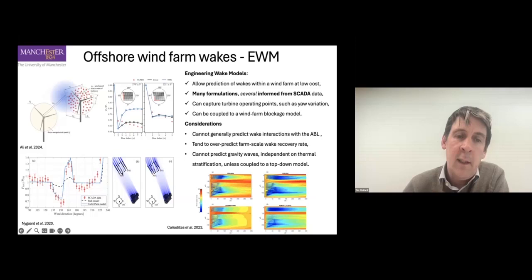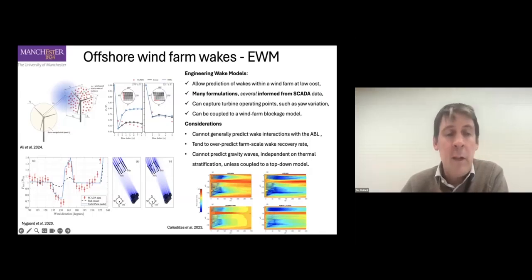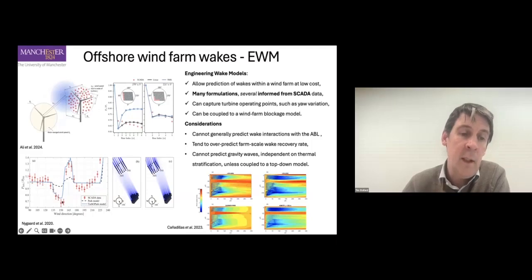This was a comparison to SCADA data along the front row, looking at the variation of the SCADA data with wind heading for this second farm. You can see the SCADA data drops off as the wind heading approaches an angle of 150 degrees, where the wake from the front farm hits the second farm. Then as the wind direction moves further north, that wake starts missing the farm, and you get acceleration of the flow on the front of the second row of turbines, as the bypass flow from the first farm hits the second.